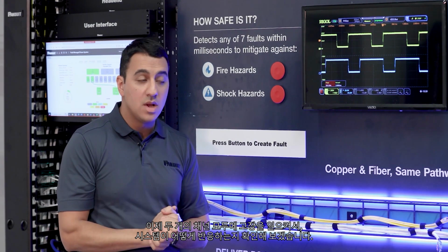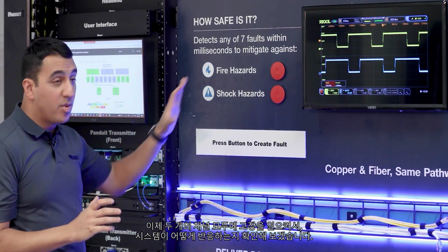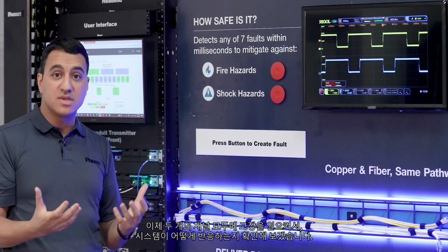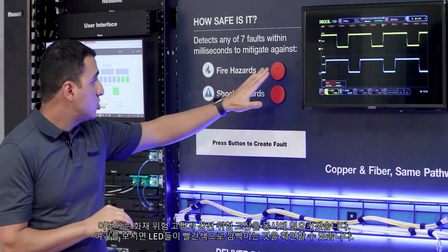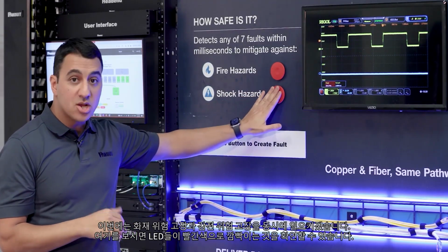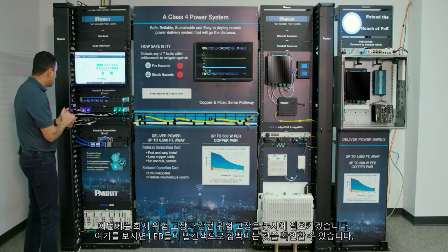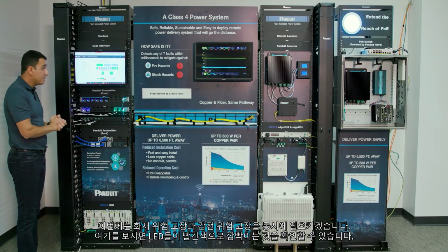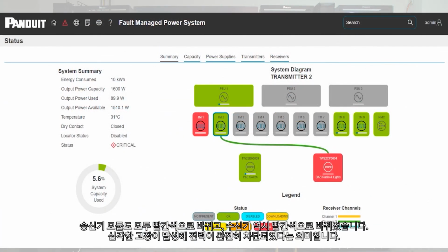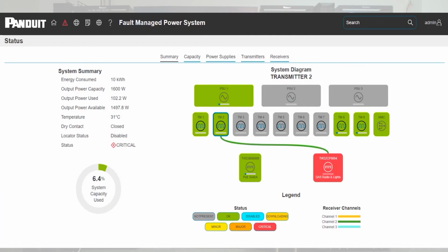Now what I'm going to do is introduce a fault to both of these channels to see how the system behaves. I'm going to introduce a fire hazard fault and a shock hazard fault. If I go quickly here, you can see the LEDs blinking red. You can see the transmitter modules went red. You can even see the receiver went red. That basically means it's a major fault, you lost power.